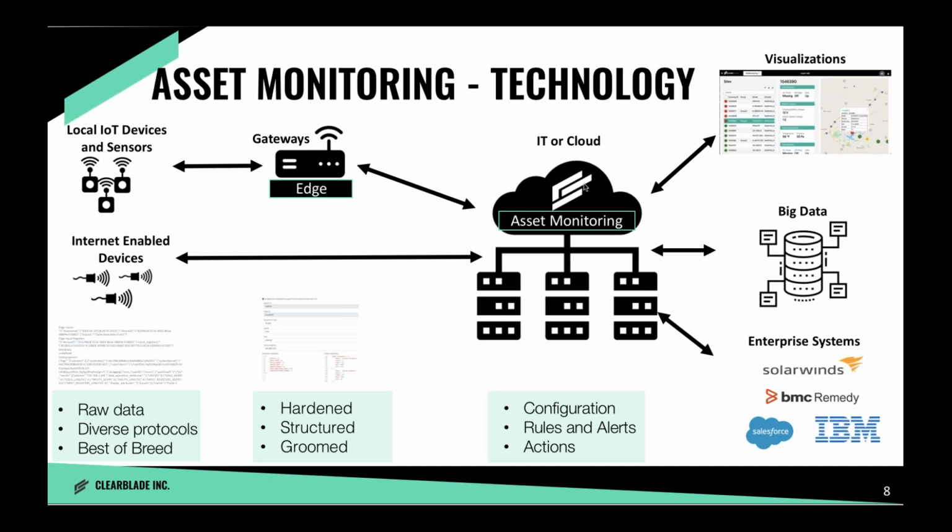It's taking that definition, that rules engine, all the stuff we configured, and moving it to the gateway where we have computers, right? There are some great vendors out there with different ways to do LoRa ingestion or BACnet ingestion or whatever it may be, Modbus, or domain specific in railroads or transportation logistics. We take that logic and we run it down there. So the rules engine is running there. The gateway is not just an agent, so to speak, translating a protocol from one to another. It is truly processing all of the logic that exists right there on that computer. That is what edge processing is.